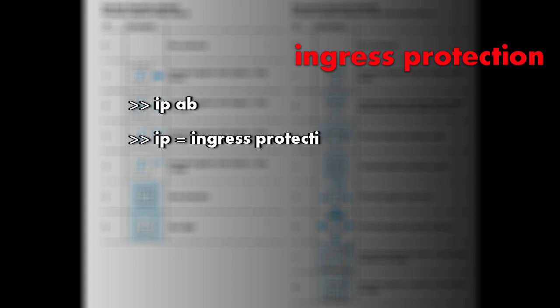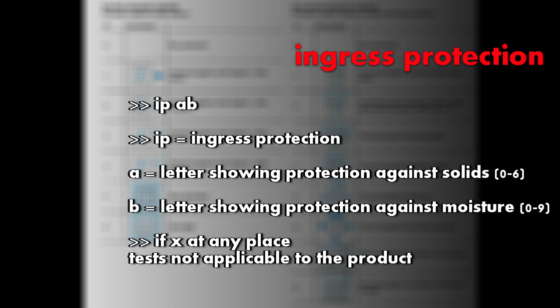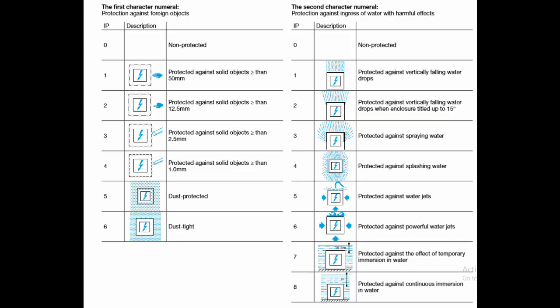Next comes the IP, ingress protection. In IP, we have generally two letters following IP. The first character numeral tells us about protection against foreign objects or solid foreign objects while the second character numeral tells us about protection against ingress of water with harmful effects or any kind of moisture. If there is X written either in the first place or second place, it signifies that the tests are not applicable to the product. If it is 0, the product is non-protected.